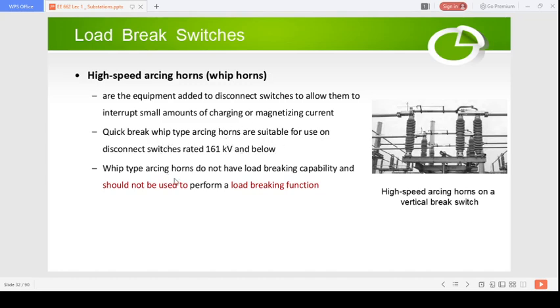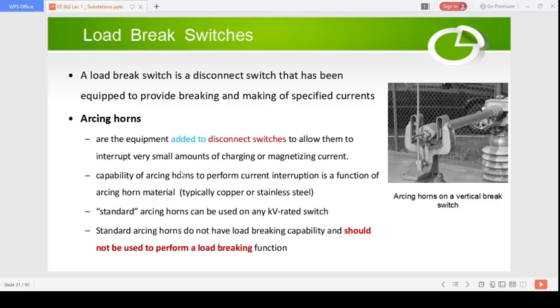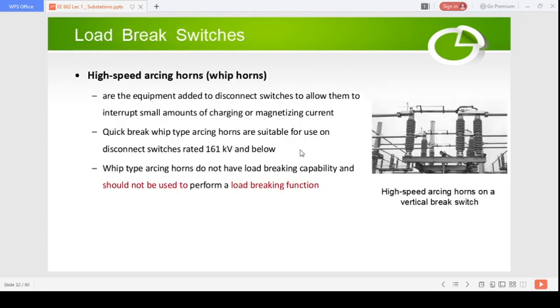This whip type arcing horn does not have load breaking capacity, as we discussed earlier for the general arcing horns, and it should not be used to perform load breaking functions. Just connecting the arcing horn does not mean it is capable of breaking the load current, but it is capable of handling a little more current than the typical isolator. These currents could be a magnetizing current or things like that. So they can handle a little more current than typical isolators.